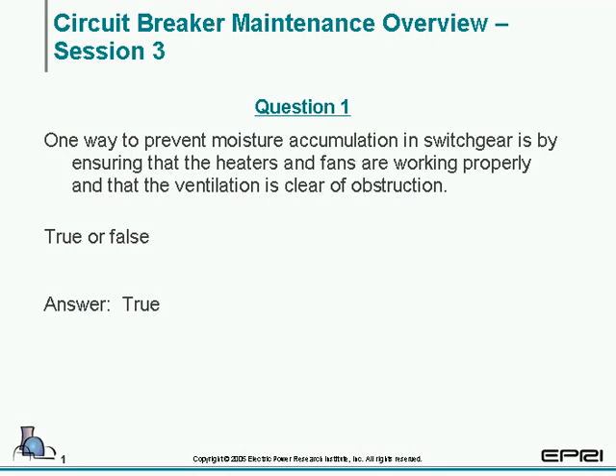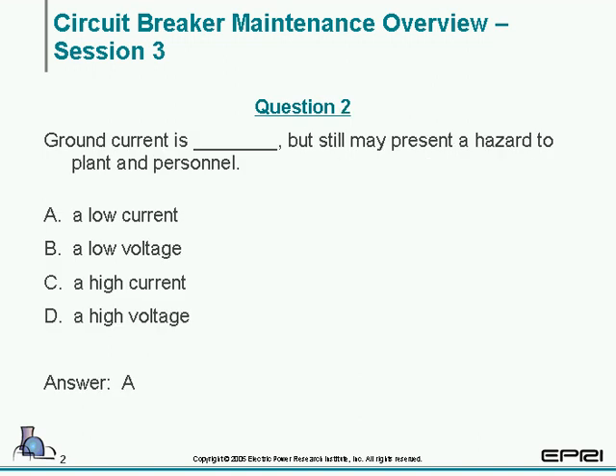Question 1. One way to prevent moisture accumulation in switchgear. Oh, I'm sorry. There's a slight delay when we turn these slides on, so apologize for that. Okay, you should have question 1 on your screen. One way to prevent moisture accumulation in switchgear is by ensuring that the heaters and fans are working properly and that the ventilation is clear of obstruction. And that is true. It's a basic preventative maintenance task that you should have.